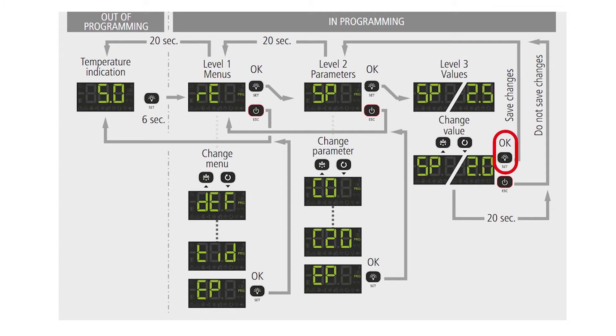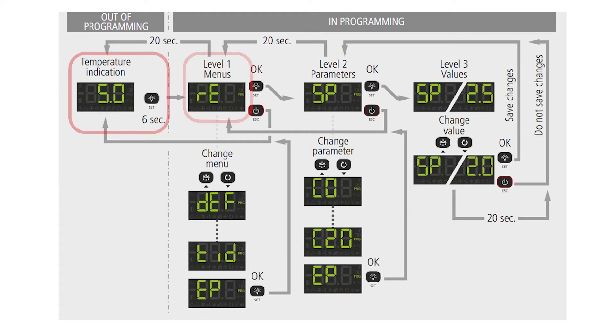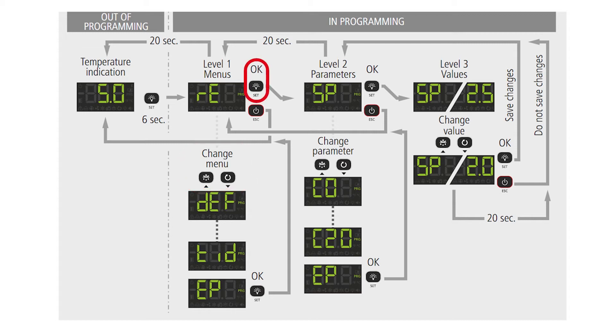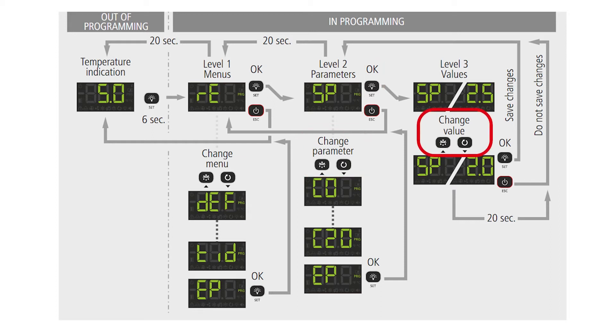Now once you have hit set, the controller will go back to the level two parameter menu. This sounds way more complicated than it really is. You can access the extended wizard parameter menu by pressing set on the controller for six seconds. This will take you to the level one menu and RE will be displayed. From there, press the up and down buttons to scroll to the level one parameter you want and hit set. Then use the up and down buttons once again to scroll to the level two parameter you want to select a value for and hit set. These level three values can be scrolled through until the correct one is shown. Hit set and you will go back to the level two values.